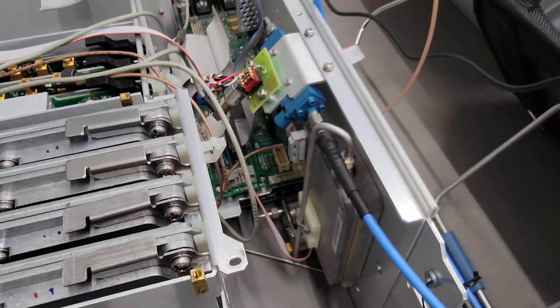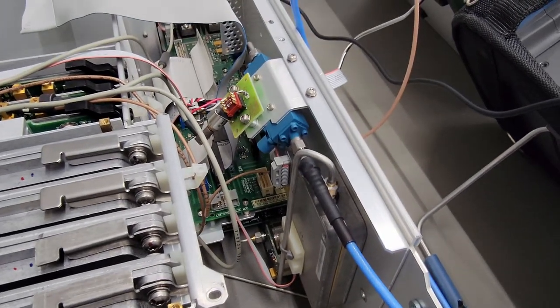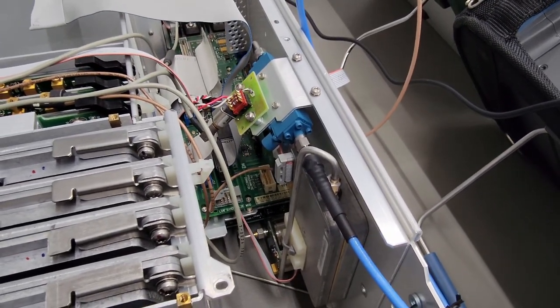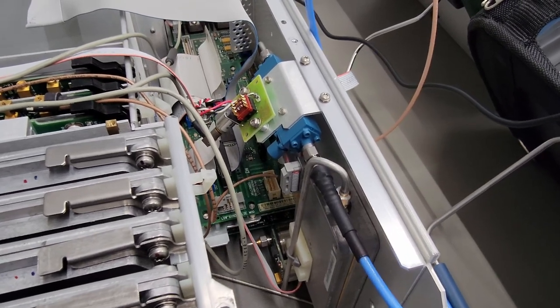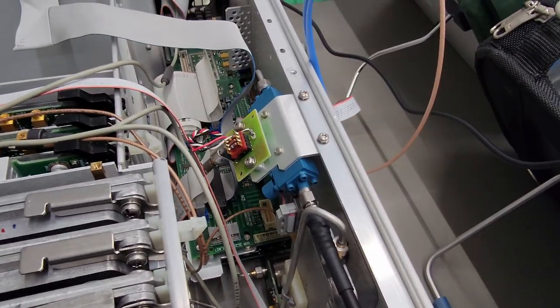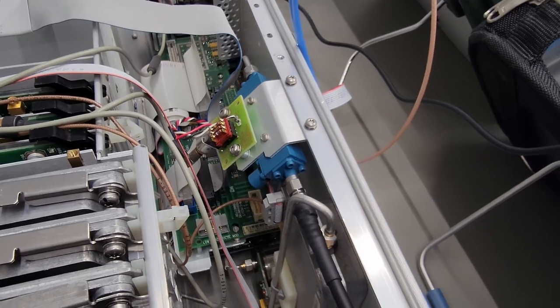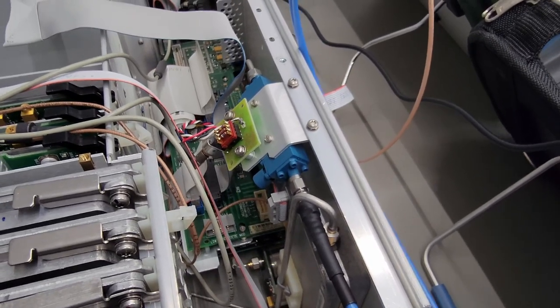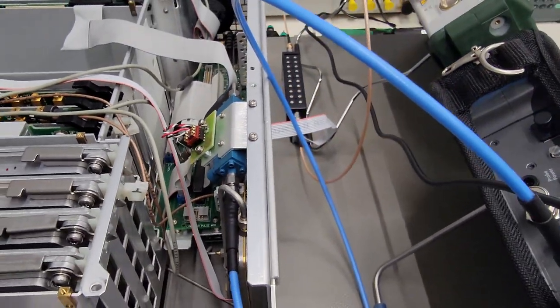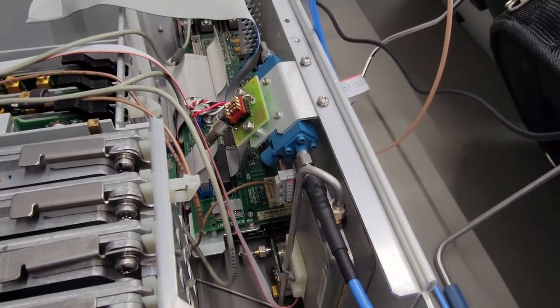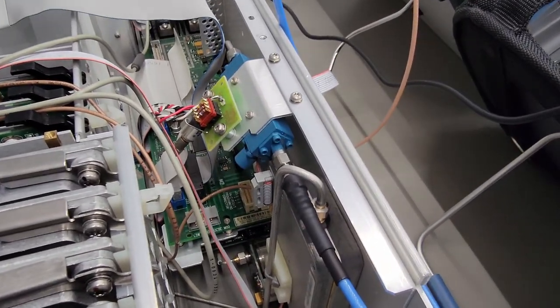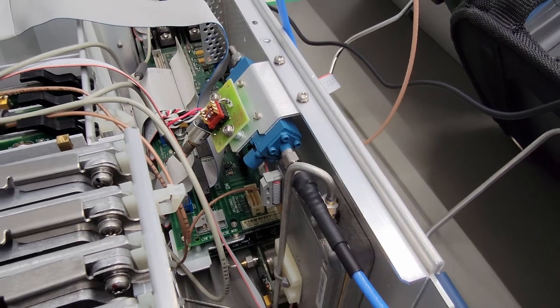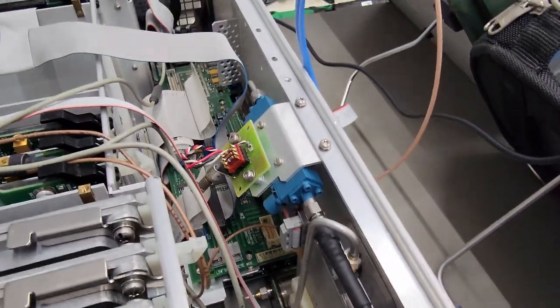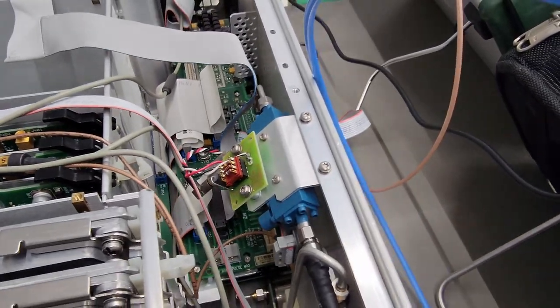So by testing it at this point, I'm ruling out any issues with the front panel connectors and the attenuator, and I'm just evaluating the signal level as it should be before the attenuator. And obviously at higher power levels, the attenuator is completely switched out of the RF path. So at higher power levels, if we have incorrect power measurements here, it means that something downstream of the attenuator is causing the issue.